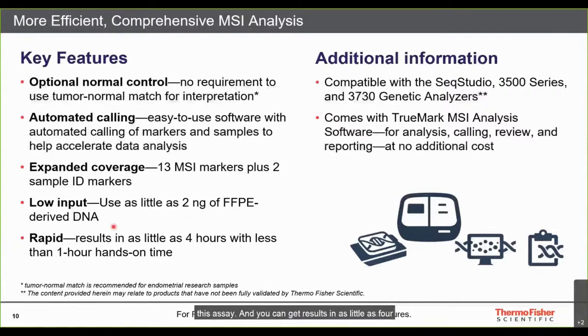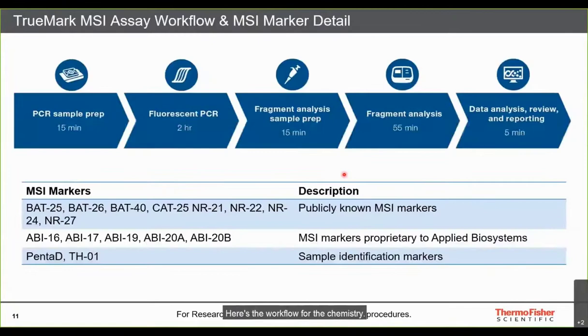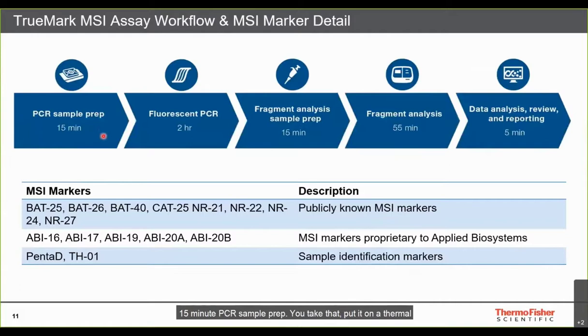Analytical validation was performed on the SeqStudio and 3500 series, and customers also report good results on the 3730. The software is provided at no additional cost. Workflow: after DNA extraction from FFPE samples, a 15-minute PCR sample prep is followed by two hours on a thermal cycler, then fragment analysis sample prep, capillary electrophoresis, and FSA file import into software — an overall MSI call in four hours.